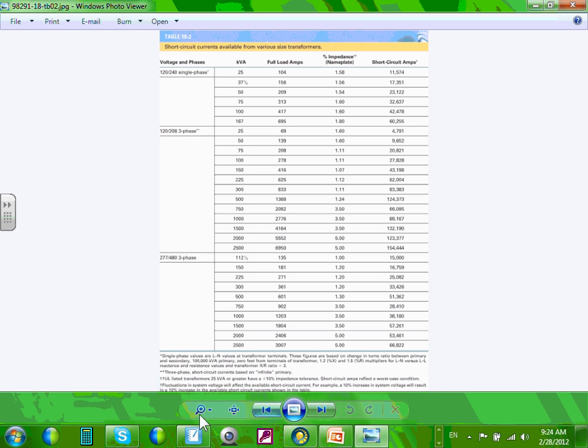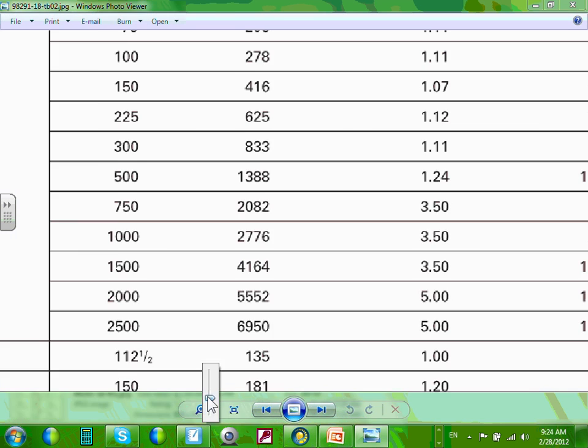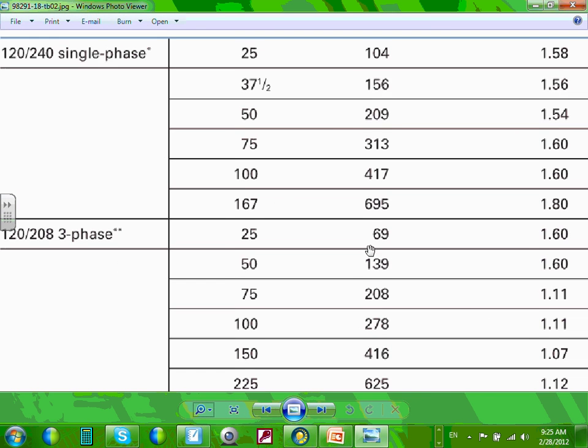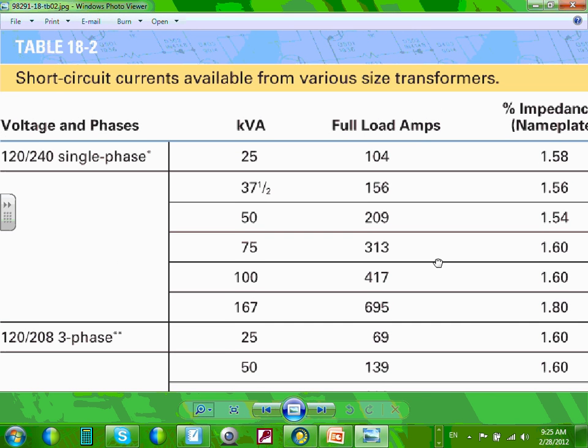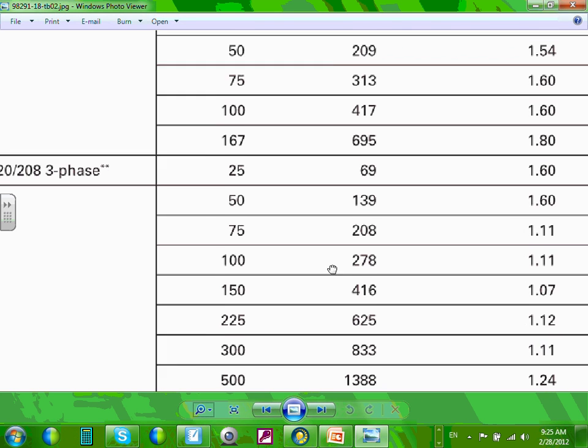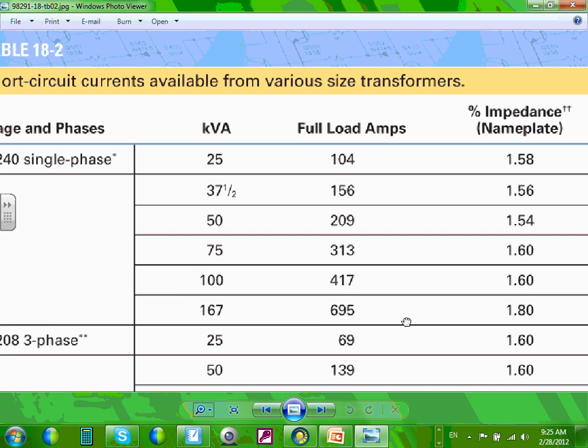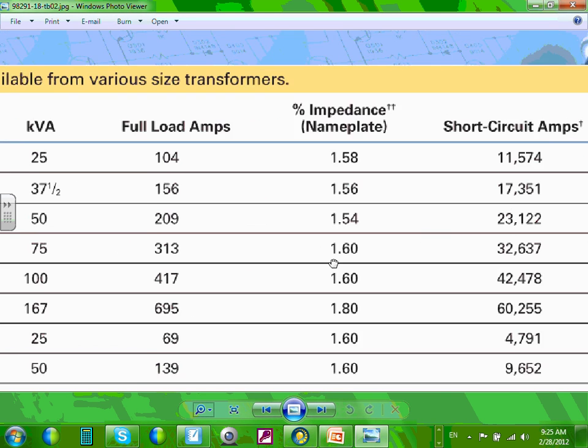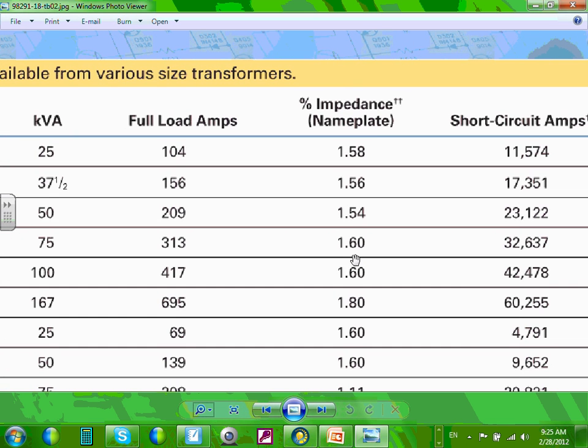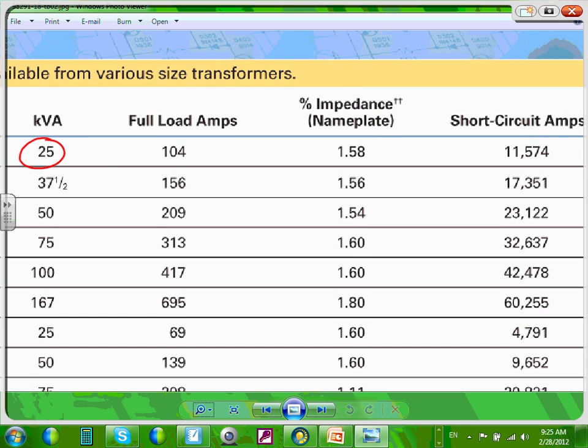This table, guys, you can have these tables in the industry, you have them in your book. Every manufacturer gives you the available short circuit for equipment. Let's say a three-phase, because we're a three-phase system. Can you guys see, it will give you the impedance and the short circuit. So let's look at this. At the terminal of this 25 kVA transformer, the full load current is 105. That's a piece of cake. Here's the impedance, and here's the short circuit.